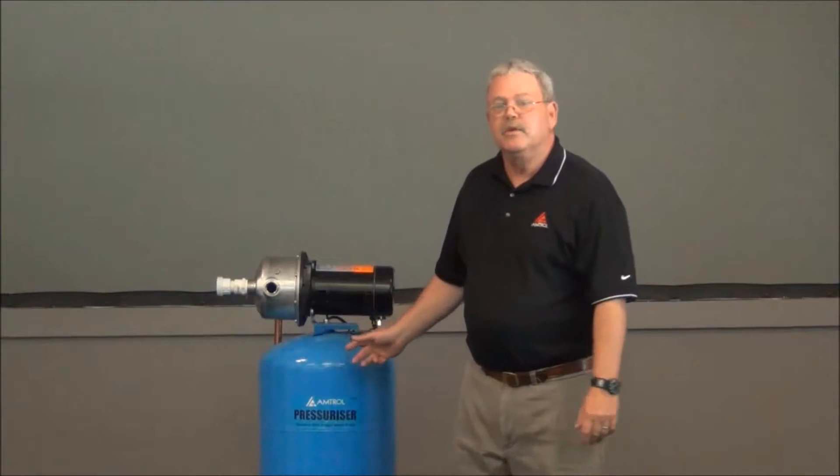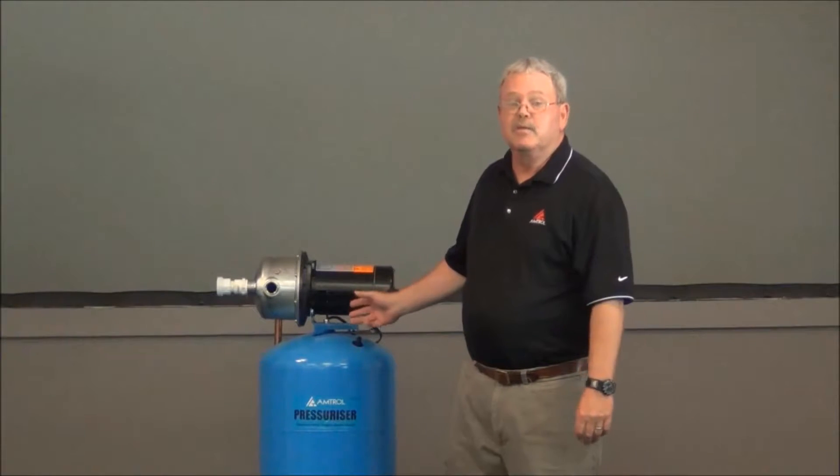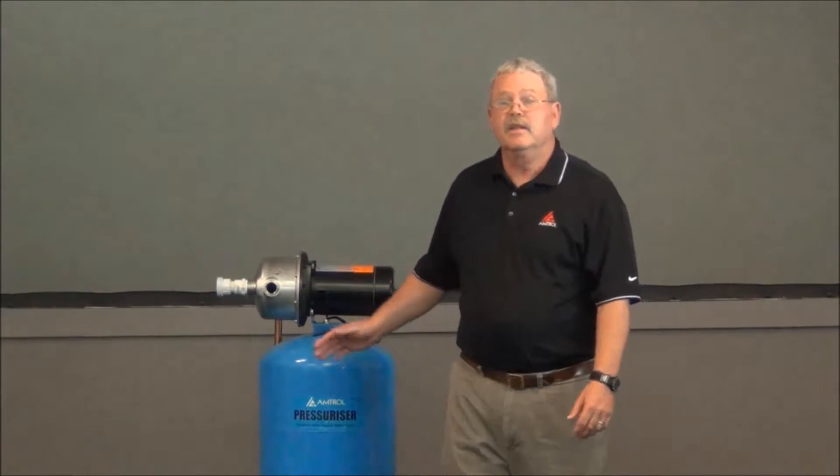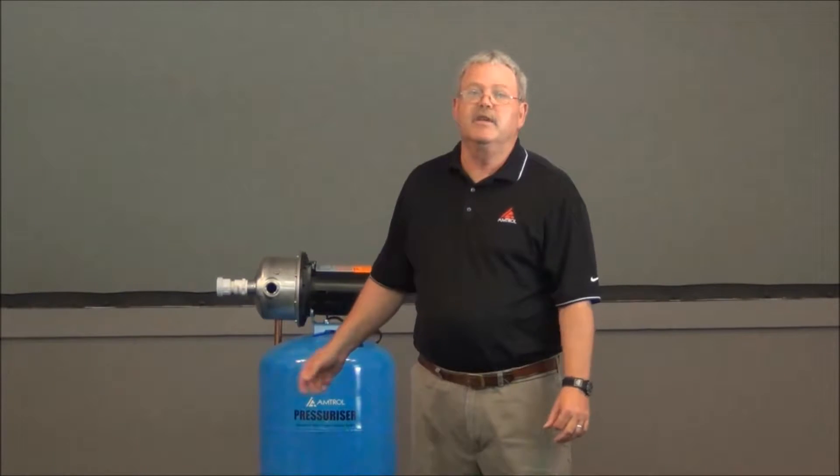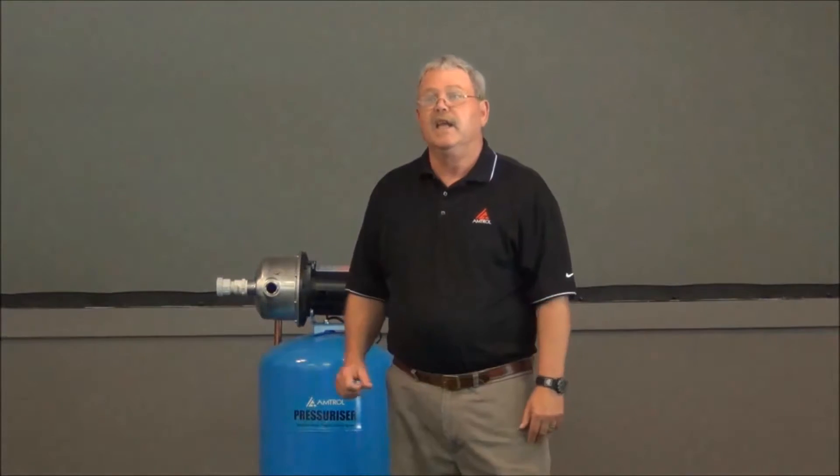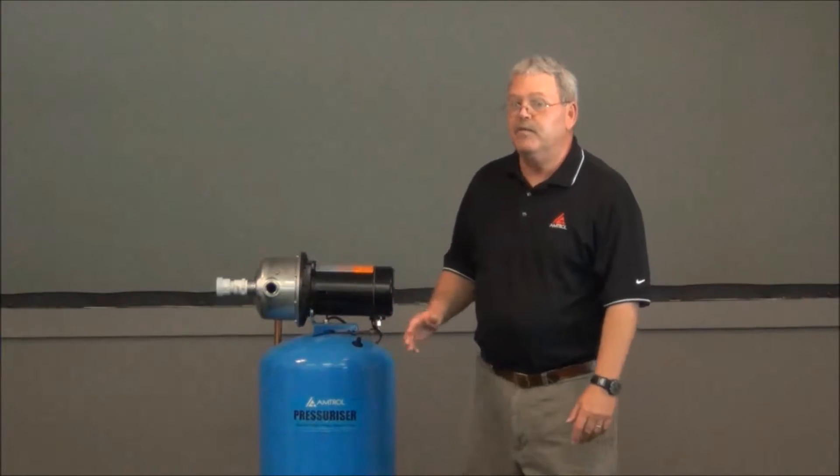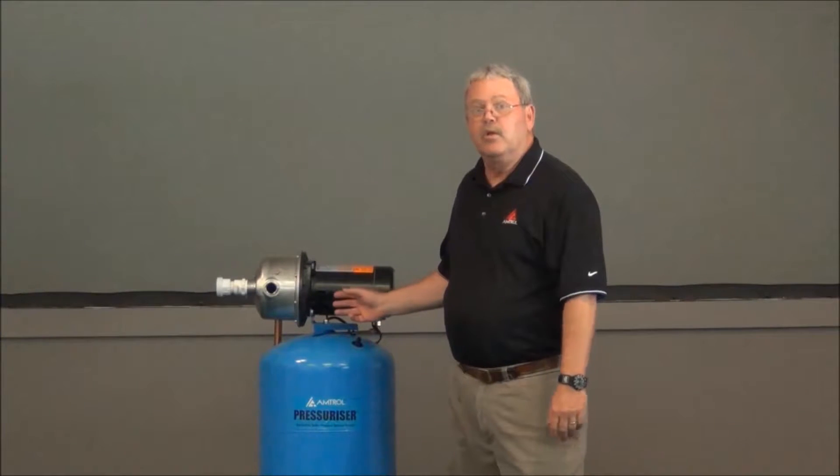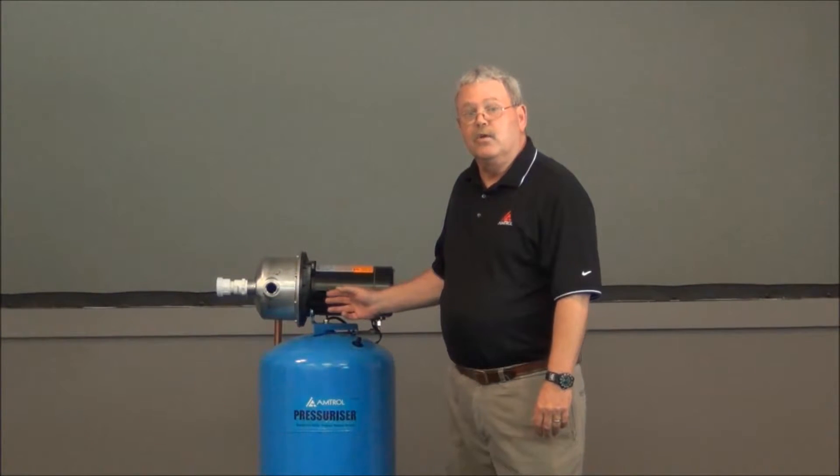Well, if it's a brand new installation it may be that it's miswired. And by that I mean this pump comes wired from the factory at 115 volts. If you've brought 230 volts to it, this pump will overheat and will go off on a thermal overload.